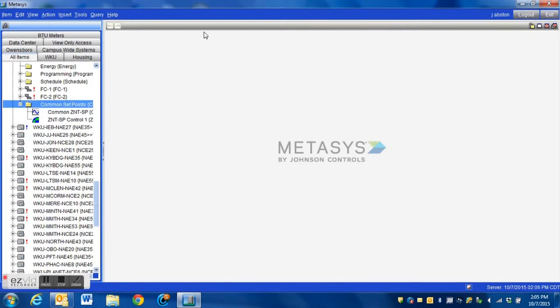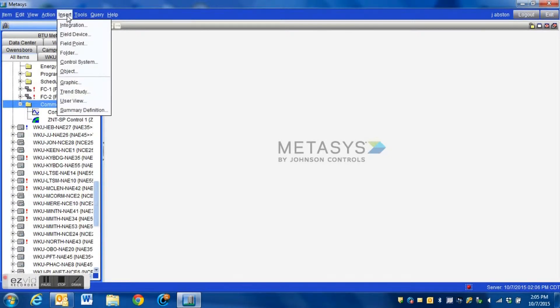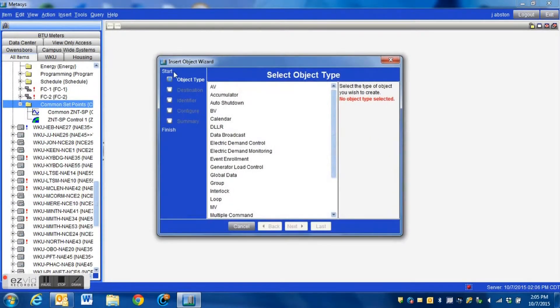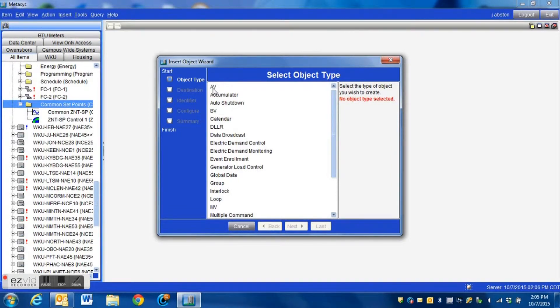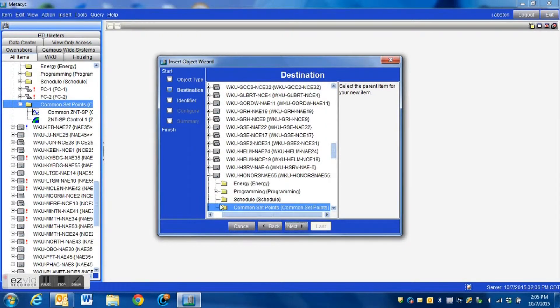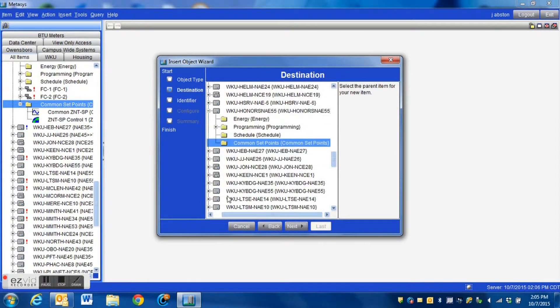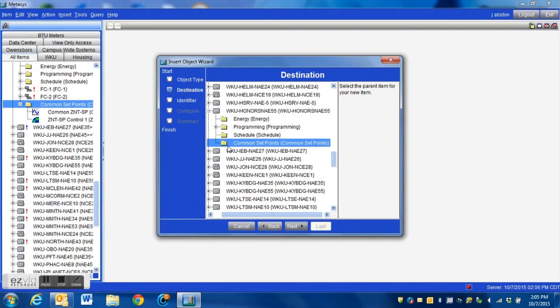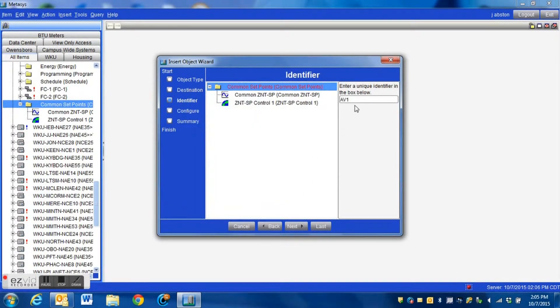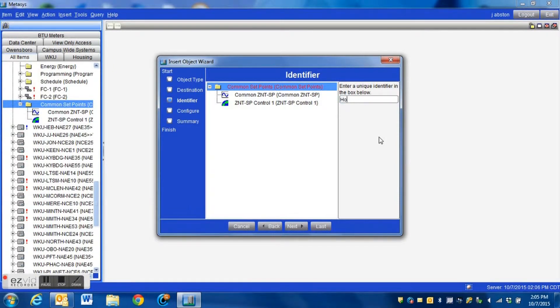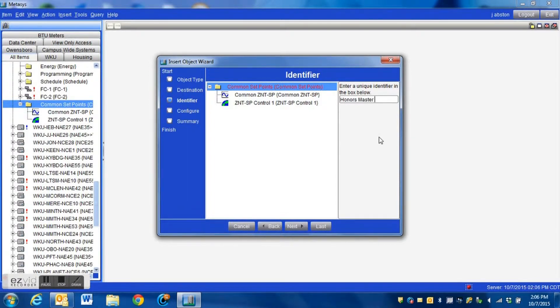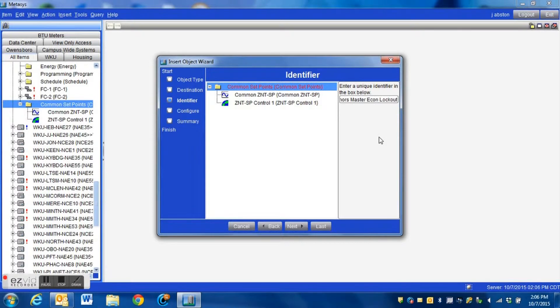The first thing that we need to do is to insert an object and we need to insert an analog value as a reference set point. We select the AV and we are going to put this in the common set point folder that we have created under this particular building device and we're going to simply give this a name, something that is a very good reference. We're just going to call it master econ lockout setpoint, something generic that will be easily recognizable on our system.